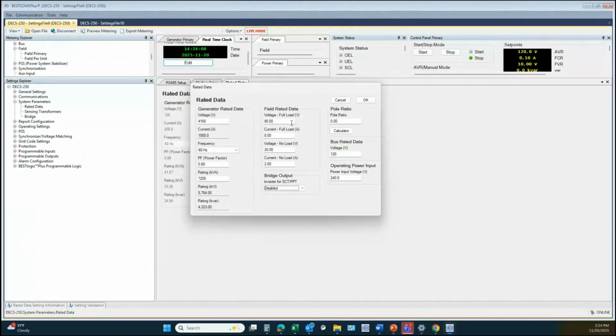But the no load values are utilized if you're trying to use the auto tuning, and when it's trying to determine a recommended loop gain, it will use that no load value. So if that no load value is not known, then again, I suggest set it to about 1/4 of the full load value as a ballpark setting.